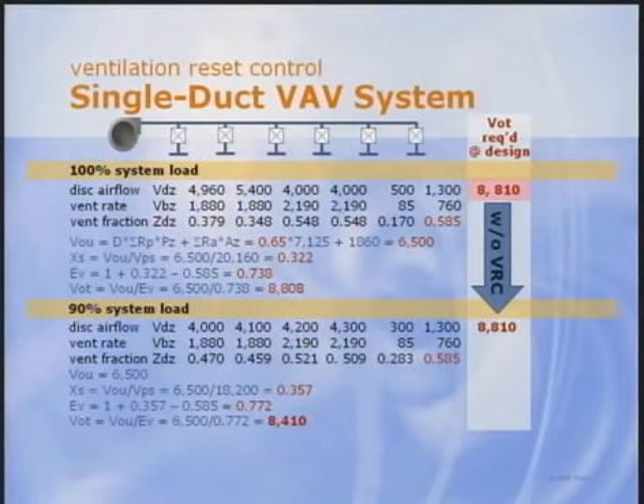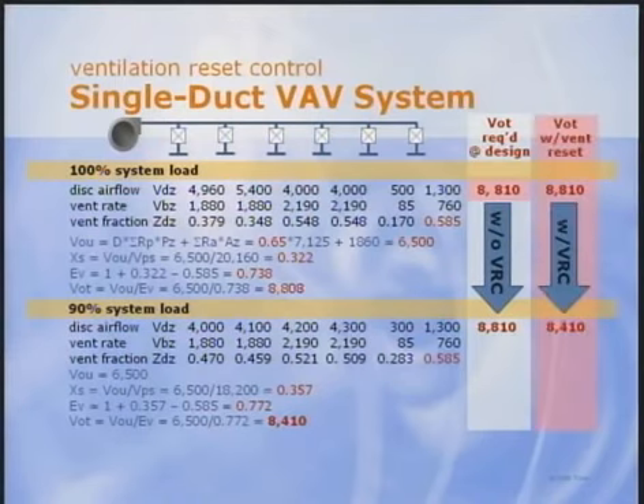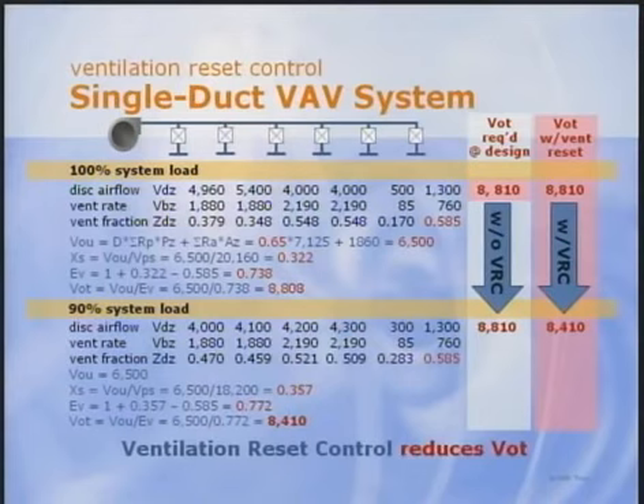If we don't use ventilation reset control, the system needs design outdoor air at all loads. But as you can see, by solving the equations again at the 90% load condition shown, the system only needs 8,400 CFM for proper ventilation. System ventilation efficiency goes up because less unused outdoor air leaves the building in the exhaust air. Conservatively designed multiple zone systems always need less than design outdoor air at part load. This is why ventilation reset control is one good way to dynamically reset intake airflow and save energy.